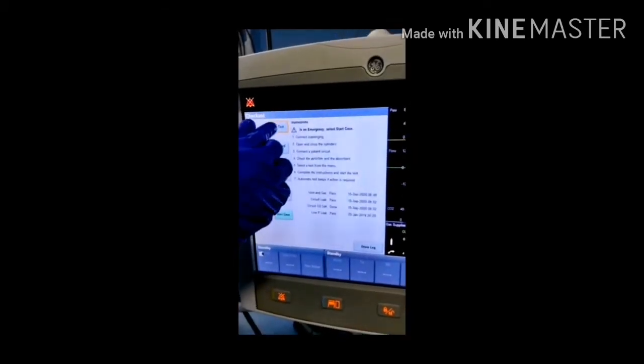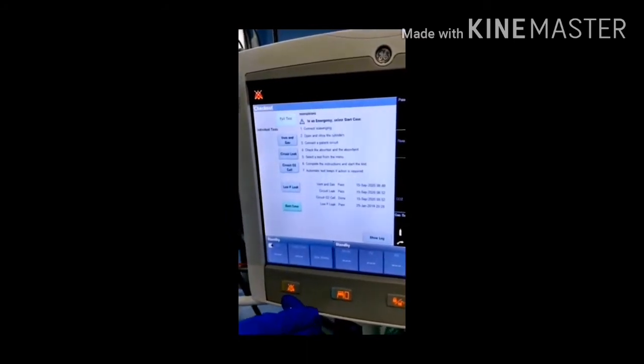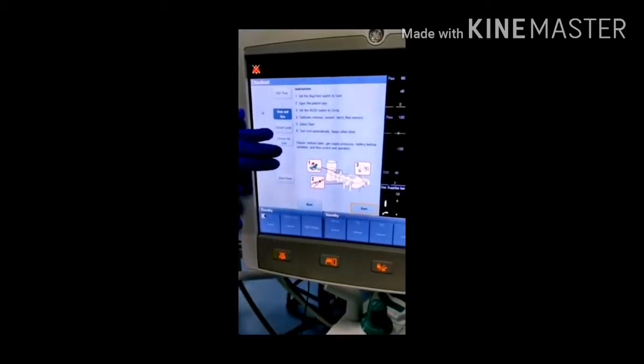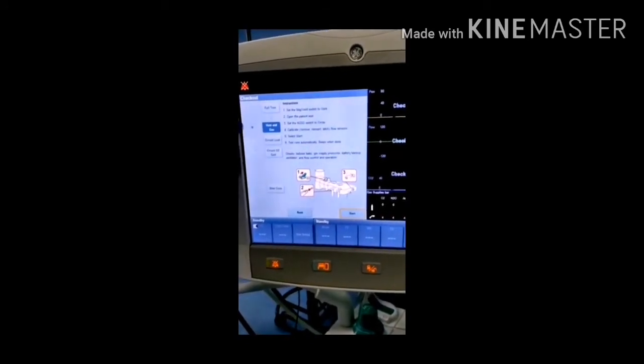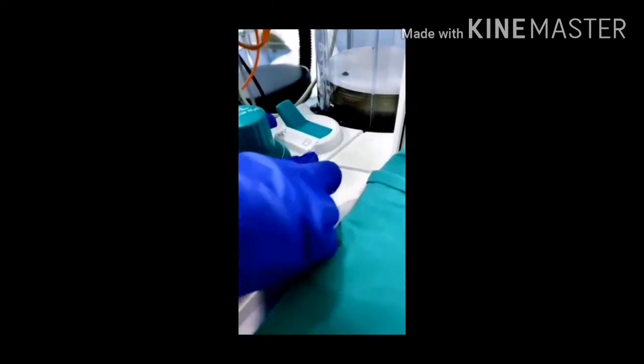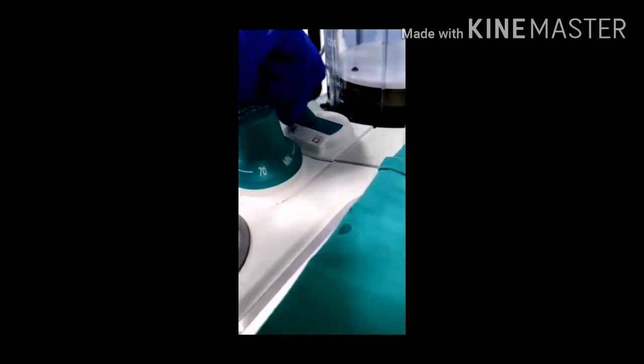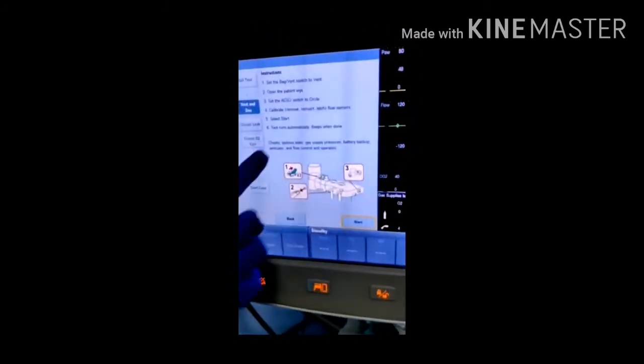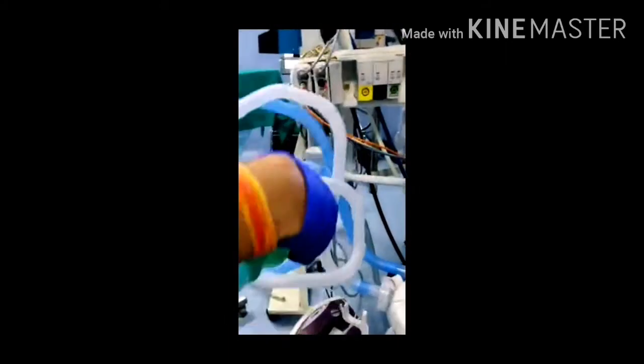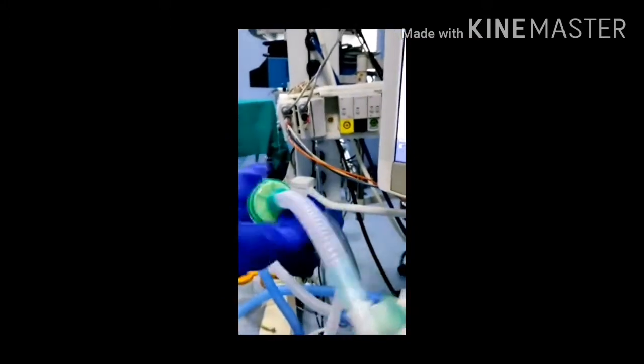We will go ahead with the full test, which would help to rectify if there is any leakage and do the necessary changes before the cases. So we will do a full test. So as you can see, the instructions are given, you just have to follow and go step by step. So here for vent and bag, I will have to put this switch as explained. This is the vent which shows the bellow jar symbol, and for Ambu this is a symbol of a bag. So just switch it to vent, open the patient Y. This is the Y circuit, you just have to keep it open, don't occlude it. ACGO switch to circle. This is the ACGO switch. When you are connected in a vent position, you just have to put it on circle.